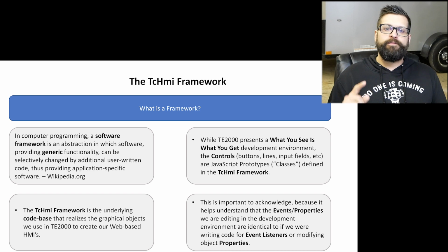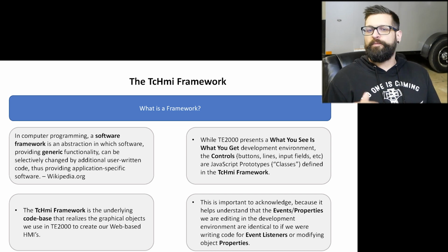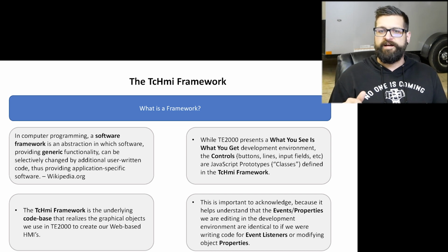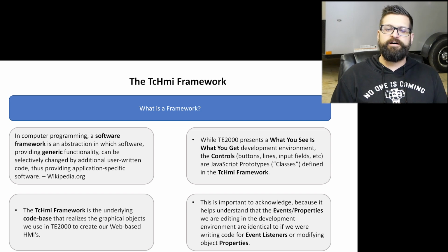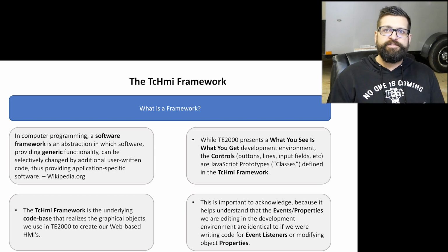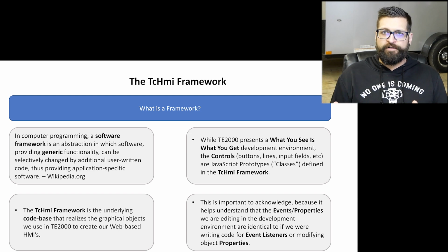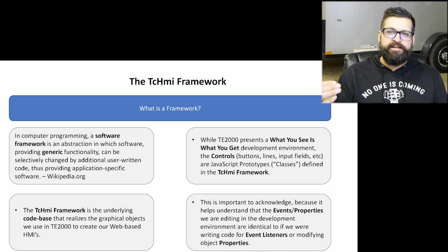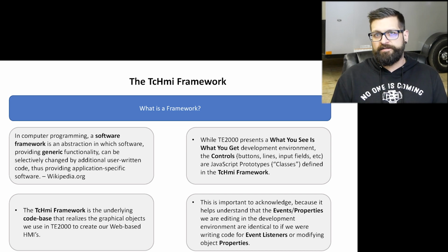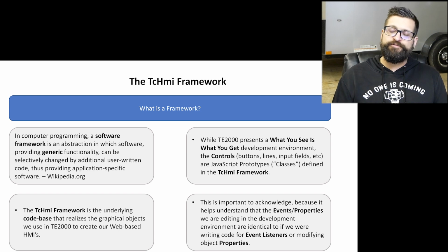One, while in the engineering environment, when I say on touch or on press, when an operator touches this button on the touchscreen, I'm going to cause some action to happen. Well, really, what's going on is the TcHmi Framework for a button has added an event listener on touch, and you're just triggering that event listener, for which you've written some code to do what you want it to do. And then they handle that in the background: okay, the event listener has been triggered, let's do this thing that they have then programmed.